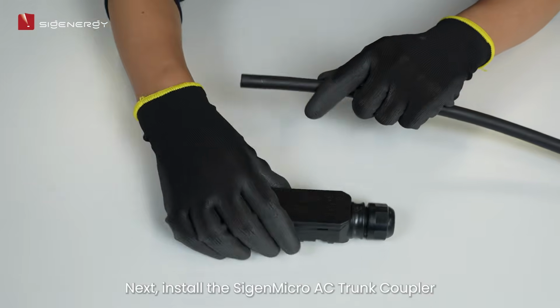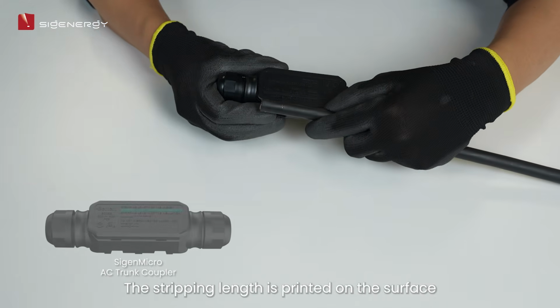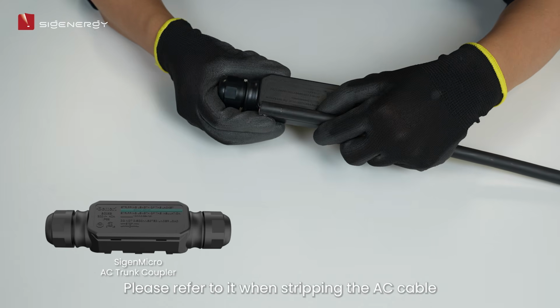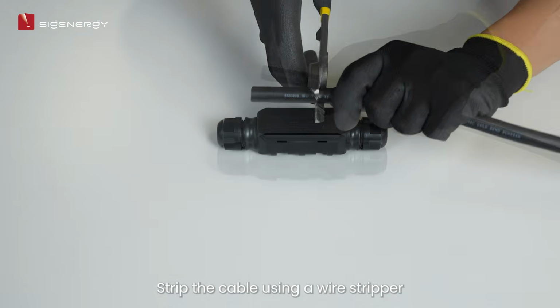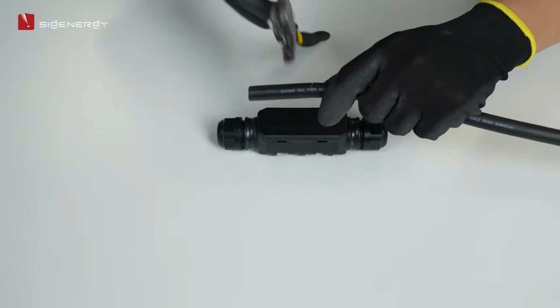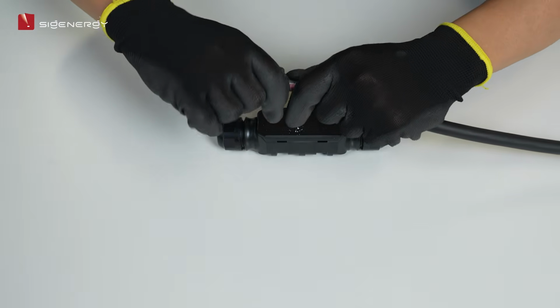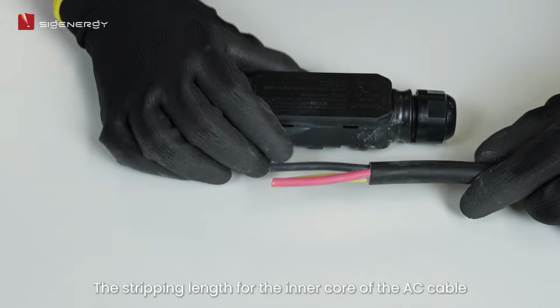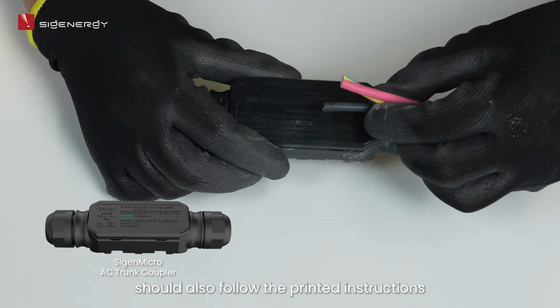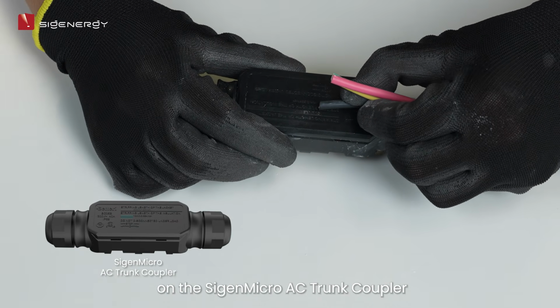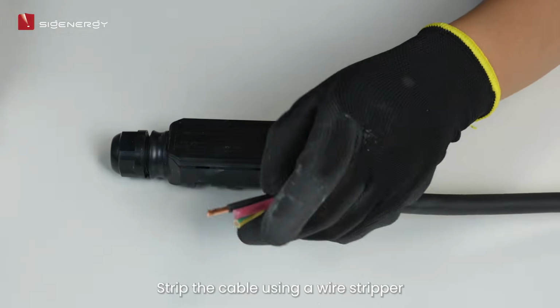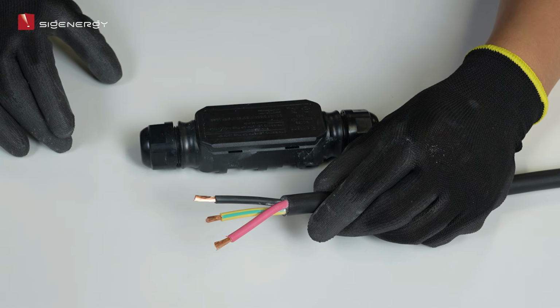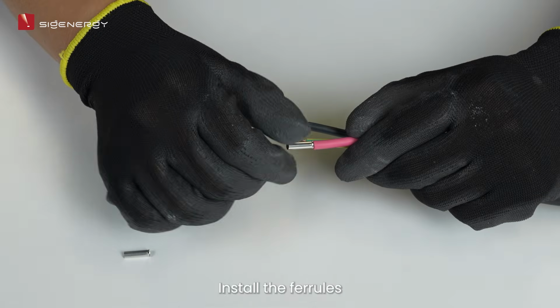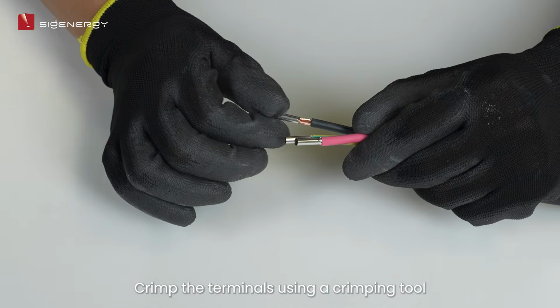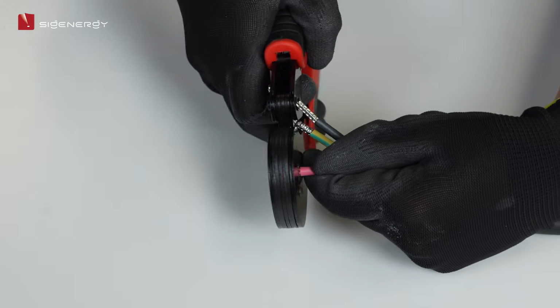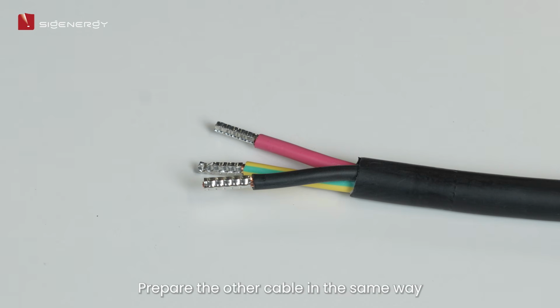Next, install the SigenMicro AC trunk coupler. The stripping length is printed on the surface. Please refer to it when stripping the AC cable. Strip the cable using a wire stripper. The stripping length for the inner core of the AC cable should also follow the printed instructions on the SigenMicro AC trunk coupler. Strip the cable using a wire stripper. Install the ferrules. Crimp the terminals using a crimping tool. Prepare the other cable in the same way.